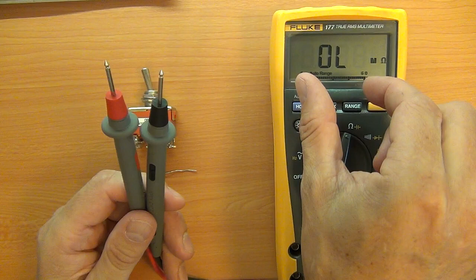If we have it in the up position like we did before, and we put our two probes between those two points, you can see we've got the overload on the screen because there's no reading. There's no continuity between those two points. I should go to these two, because depending on where the switch is, it could be either of those. If I switch it this way, there's no continuity there. We go here, and there we go. We've got that 0.2, 0.4 now.